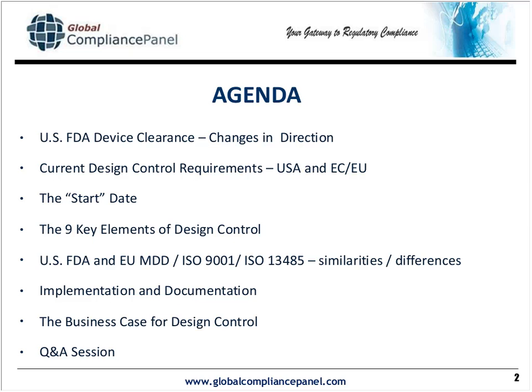So I want to emphasize the fact that design control is required under 21 CFR 820.30, but we appreciate the fact that it makes sense to do it anyway. And some of the companies I worked for in the past did it that way. They may have called it project control. They may have called the resulting document a project history file as opposed to design history file, but it was a way to control changes. And that's what the FDA recognizes.